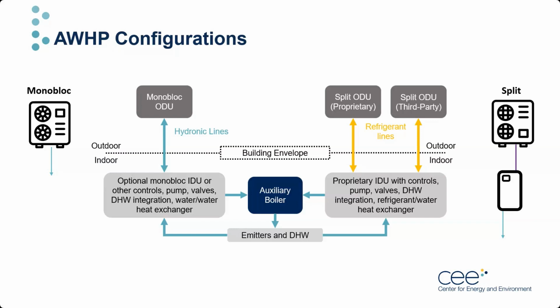In what we call a third-party split system, the ODU can be any compatible air source heat pump outdoor unit, which works fine for this type of system because the refrigerant to hydronic heat exchanger is in the IDU and is therefore external to the outdoor unit. The benefit of a monoblock is that the ODU is pre-charged with refrigerant and therefore does not require refrigerant work at time of installation, whereas the split system will be charged with refrigerant on site.